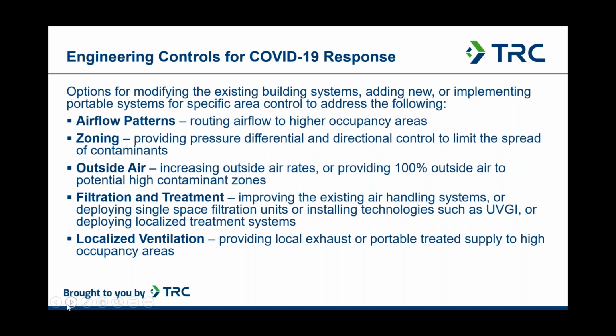If through that inspection and recommissioning process, we find that the ventilation systems are not adequate, not up to code or standard, we do have options available to us to modify the system. And again, those options include things such as changing airflow patterns within the building, zoning, increasing outdoor air introduction, the addition of increased filtration and treatment of air, and the use of localized ventilation.